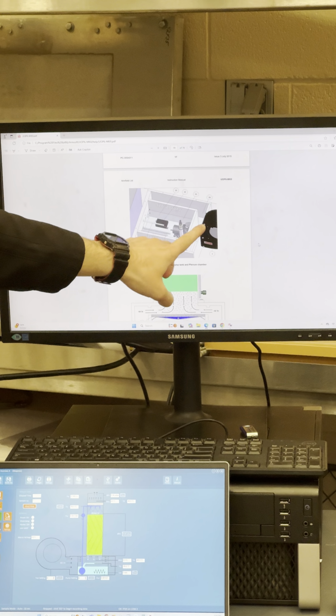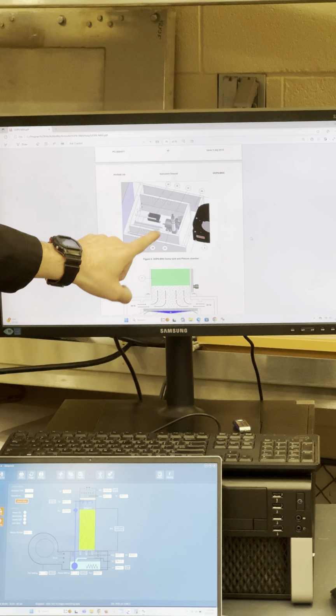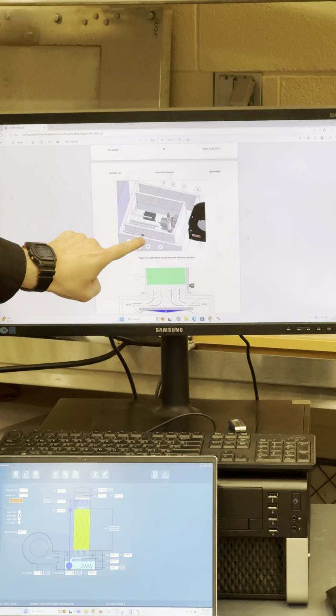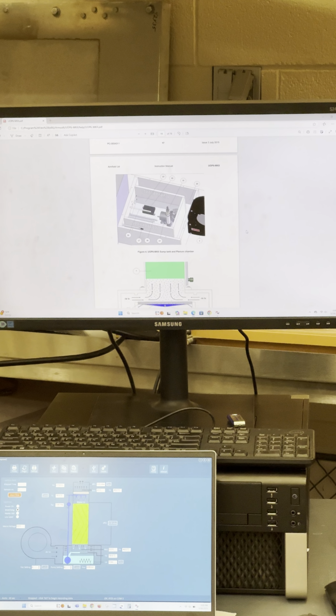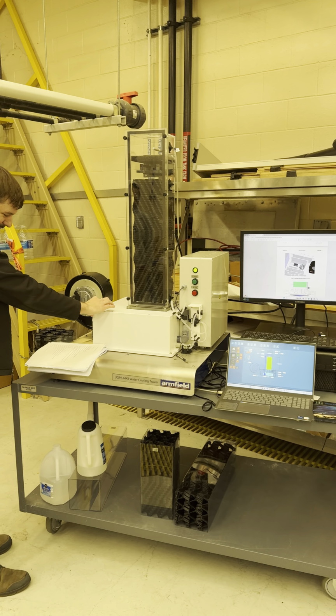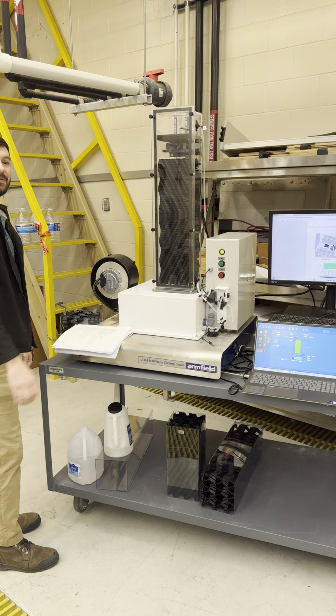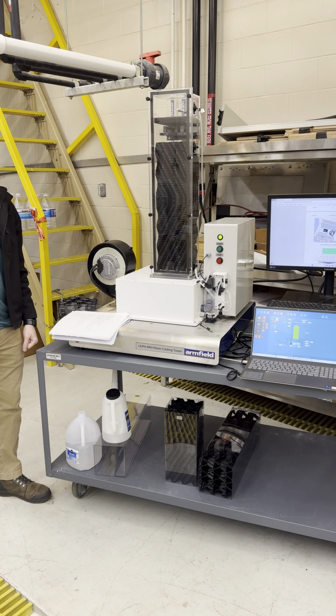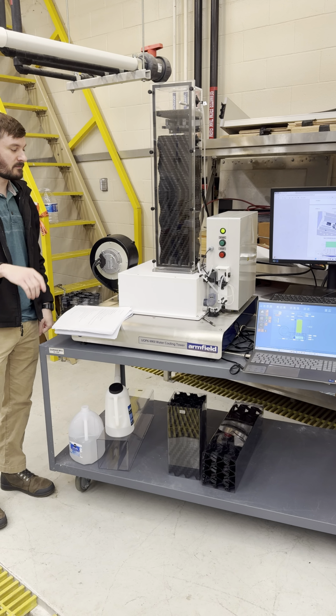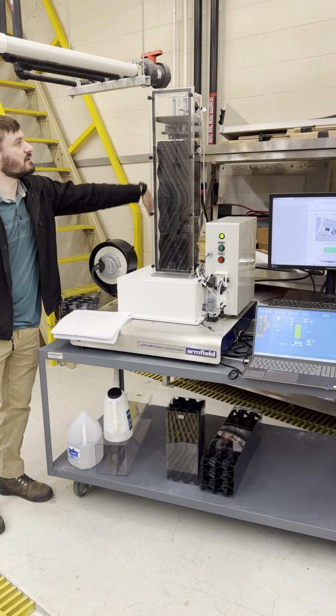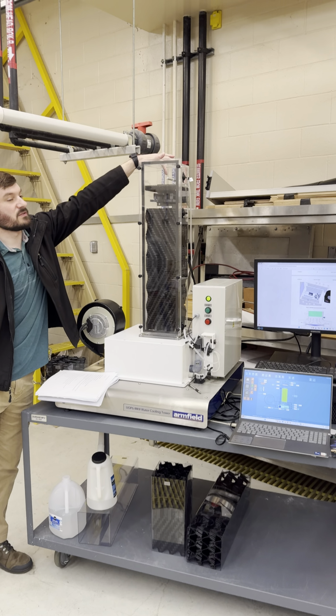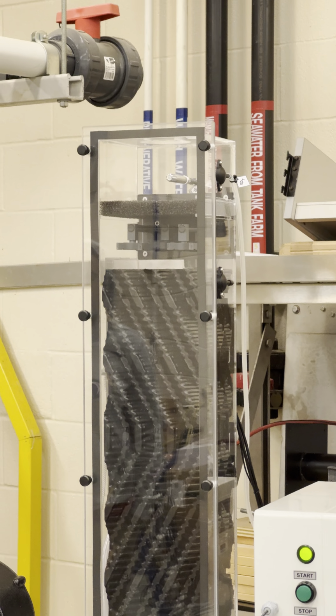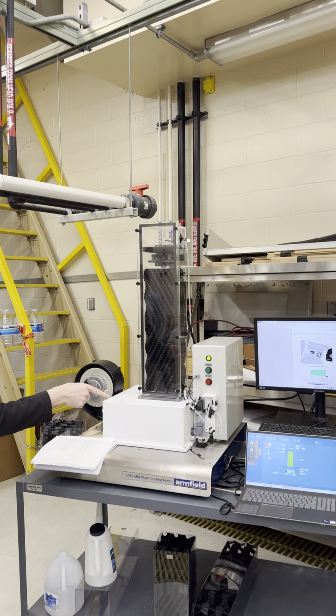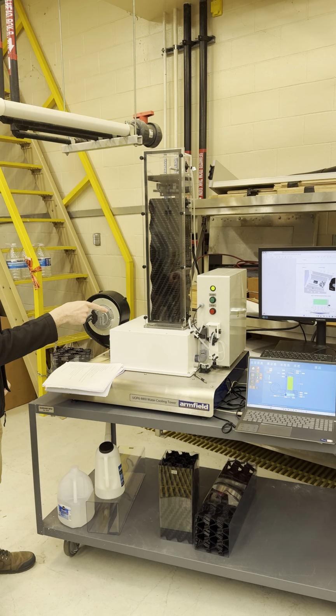So the air is coming in, filling the space right here, comes through these slots and comes up this center part. You see this little probe right there. So inside what's called the plenum chamber, that's where your relative humidity and temperature sensor combined is. They're combined sensors, both in one for your air. So your air inlet's gonna be in here, and the outlet air temperature and relative humidity is here. So that's all your sensors, and then the flow, it outputs it to the software.